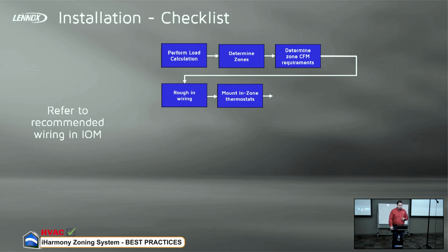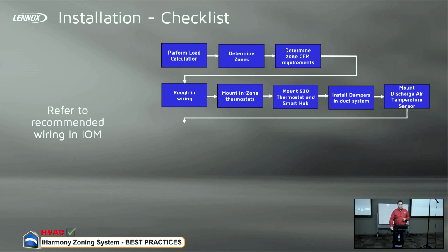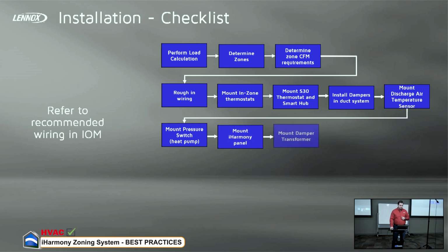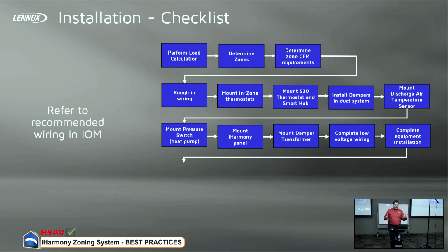So, of course, we'll do the rough-in wiring, mounting your thermostats, your S30 and the smart hub. Basically mounting all your components: your damper control, zone stats, S30, all your dampers, and mounting your discharge air sensor. That heat pump pressure switch, again, very, very critical. And then you can mount the panel, wire your damper transformer, and then wire everything up once everything's mounted. That can be real critical, just to make sure that you have everything in front of you all at once. That makes things a little bit easier when you're wiring everything up.